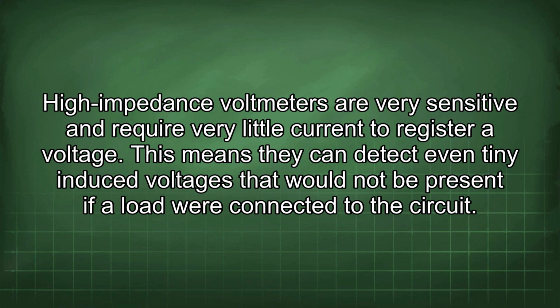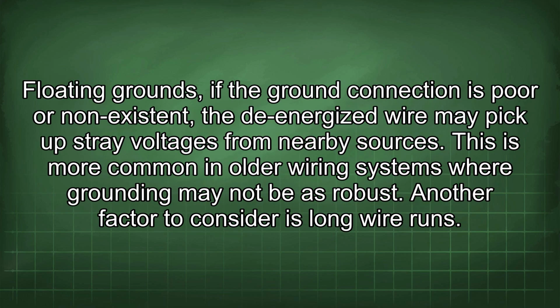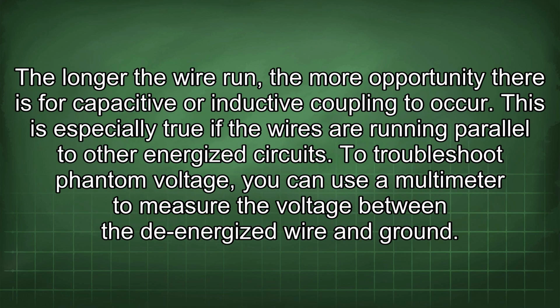Floating grounds: if the ground connection is poor or non-existent, the de-energized wire may pick up stray voltages from nearby sources. This is more common in older wiring systems where grounding may not be as robust. Another factor to consider is long wire runs. The longer the wire run, the more opportunity there is for capacitive or inductive coupling to occur. This is especially true if the wires are running parallel to other energized circuits.